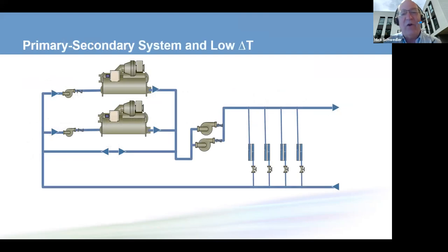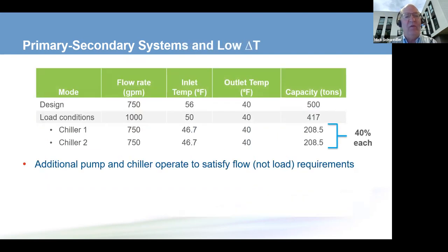Now, let's talk about how the two systems work if we have low delta T. A low delta T syndrome, some people say it can't be solved, but it can. It just has to be done out of the air handlers, out of those heat transfer devices. So in this case, we have a chiller that's designed and selected for 750 GPM to take this water from 56 to 40 degrees, and it's a 500 ton chiller.